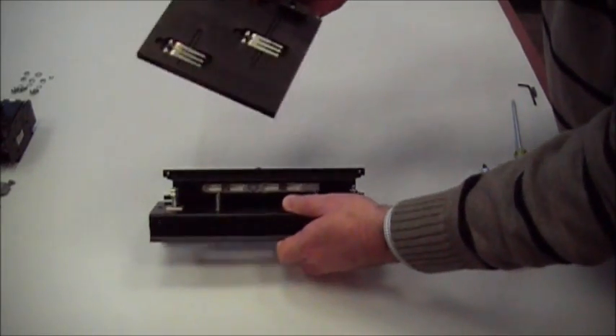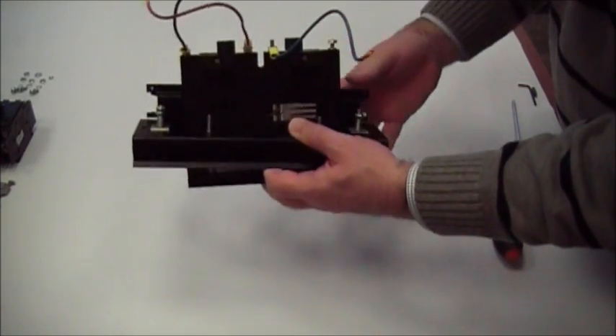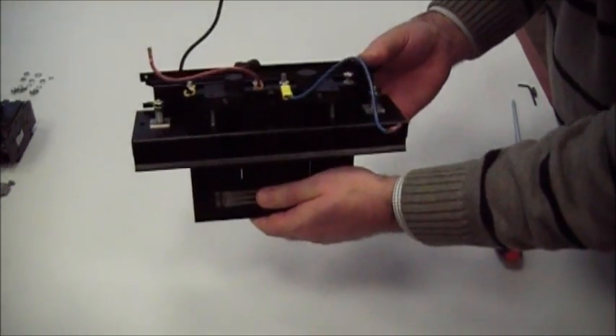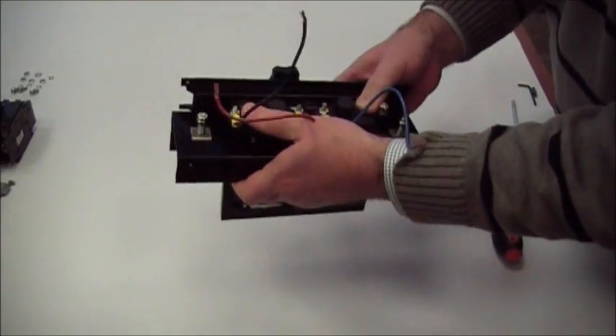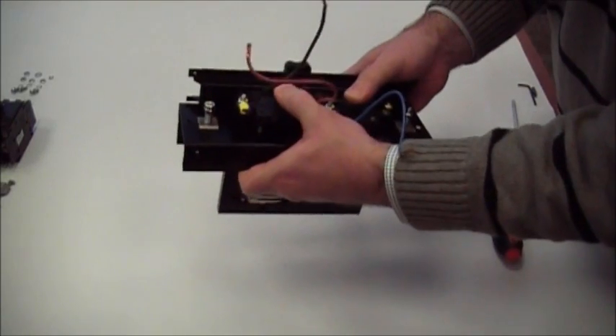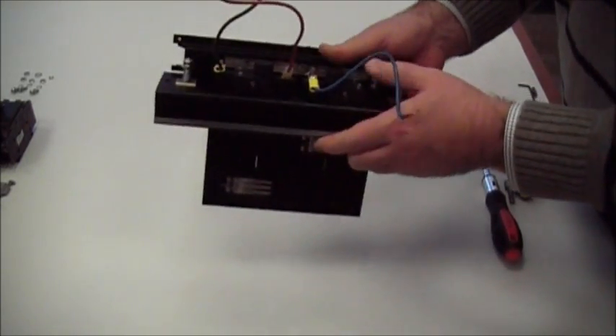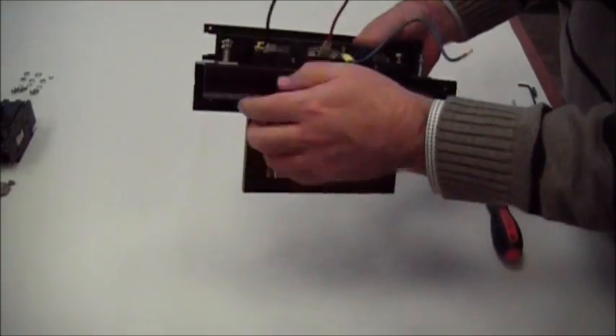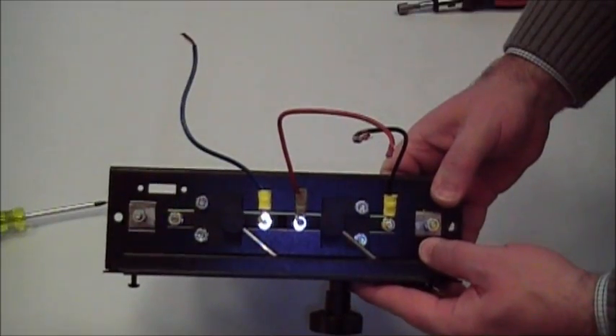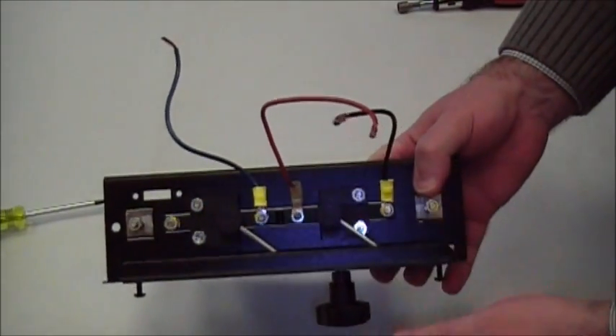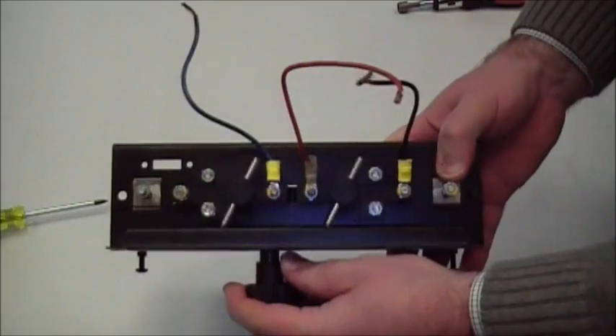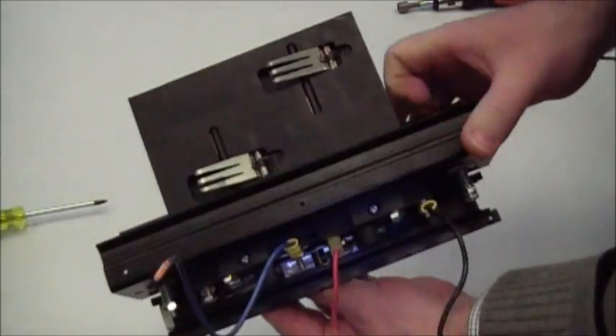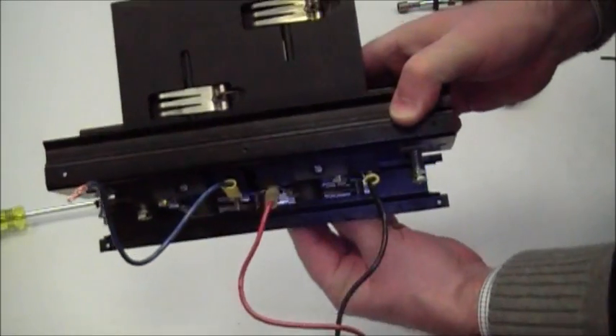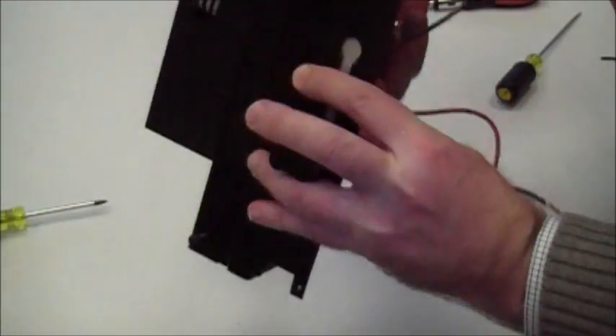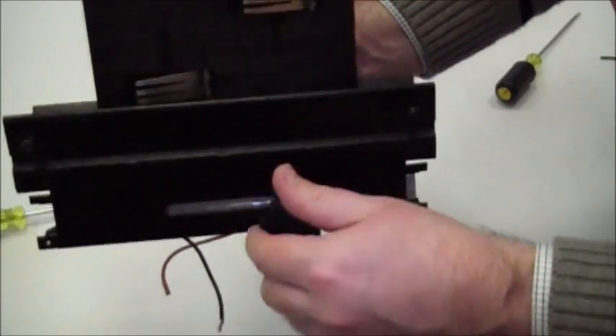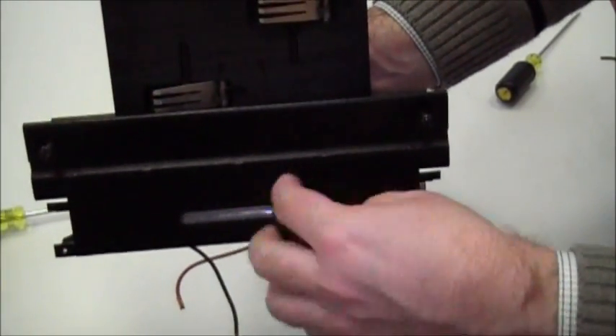So next we'll insert the paddle down through the assembly. And we'll secure that with the nuts that hold that paddle in place. Okay, now the paddle and the operating mechanism assembly is together, and you can see how sliding the lever will turn the mechanism up in the paddle, which will then force the fingers out and keep them out with a plastic piece that will keep the fingers extended once in position.